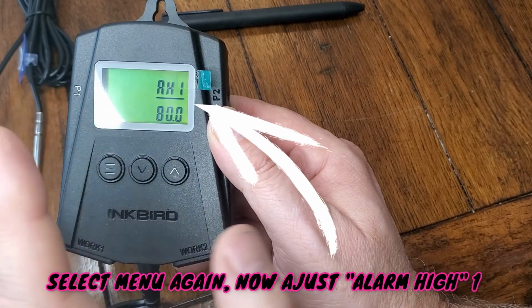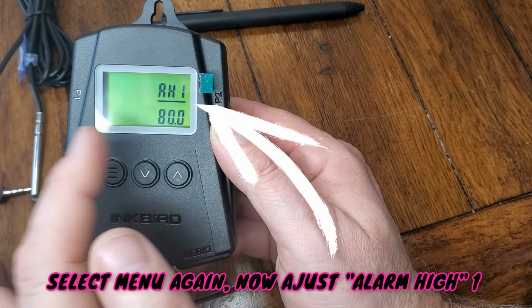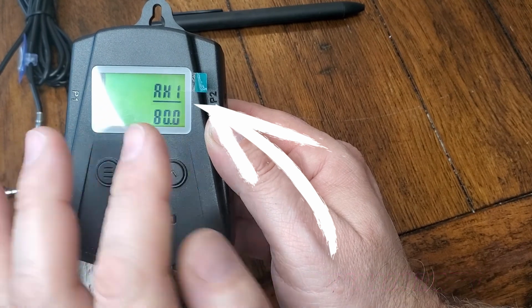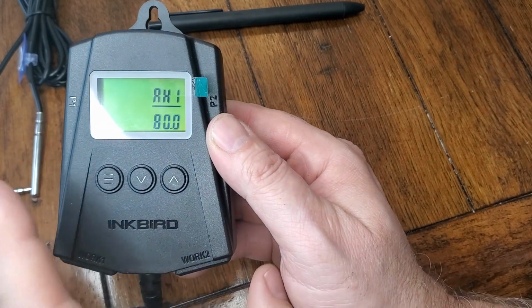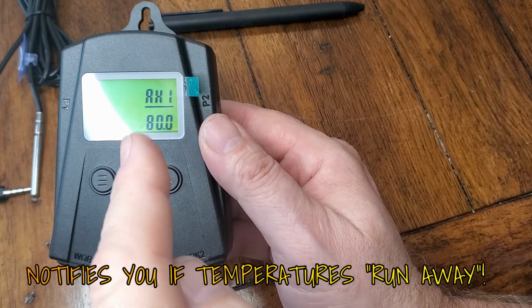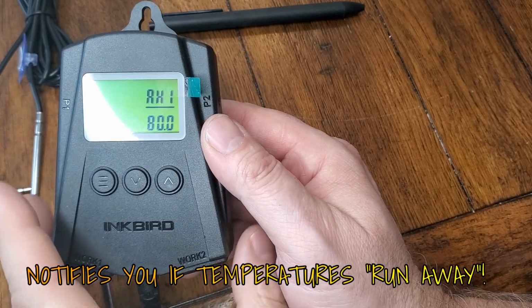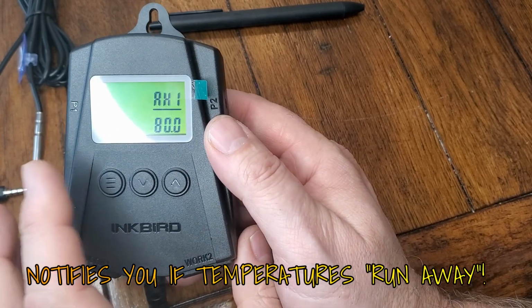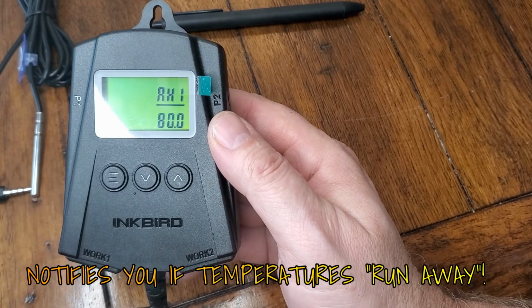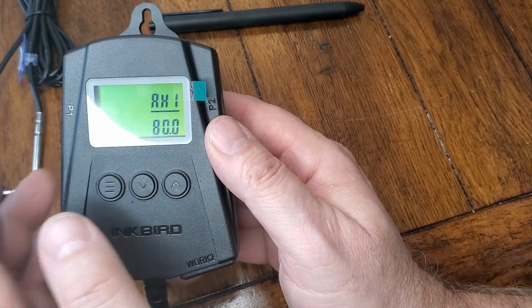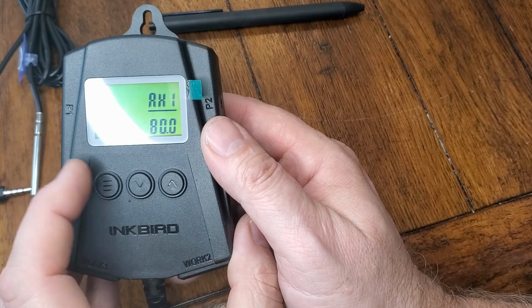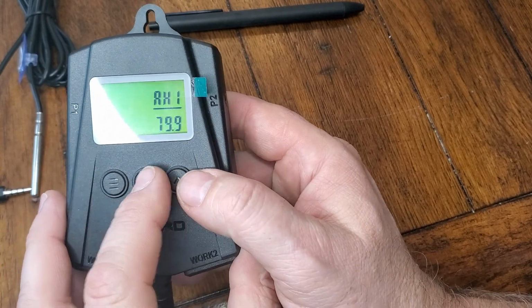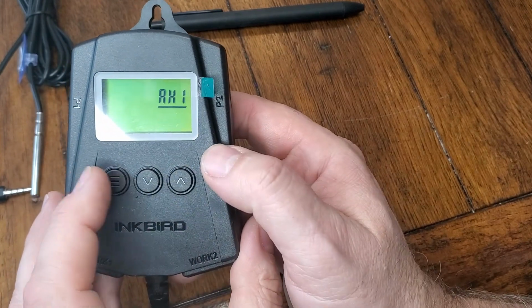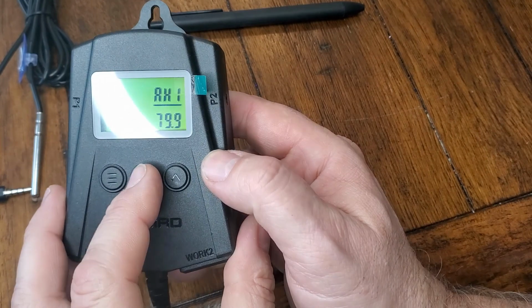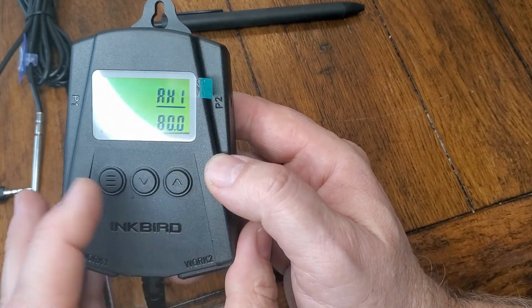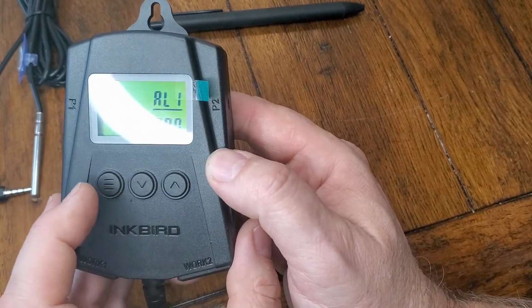Now I'm going to have alarms. Now my alarm high is at 80 degrees. So if my heat mat starts running away and the controller fails to catch it, it's going to set off an alarm to me at that 80 degree mark. That's my high alarm. So you can change it with your arrows. Just your downs to bring it down, bring it up. So I have it set at 80.